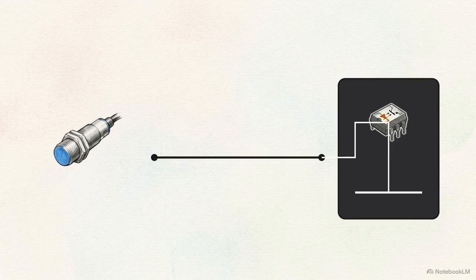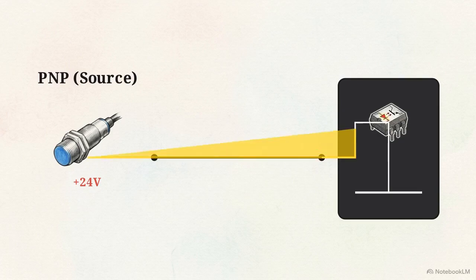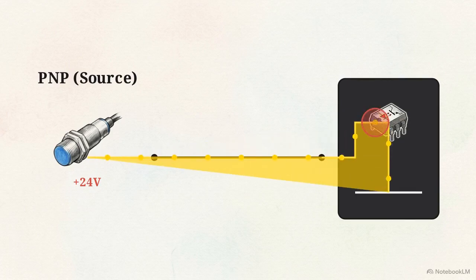In a PNP, or source input configuration, the field sensor supplies the 24-volt current. The current flows out of the sensor, through the wire, and into the PLC's internal optocoupler. Because the sensor is sourcing the current, the PLC terminal acts as the sink. It absorbs the incoming electrons and routes them down to the internal 0-volt rail to complete the circuit.